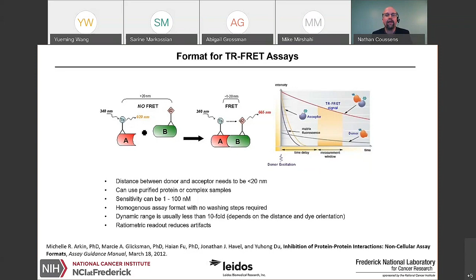And the advantage here is that when you initially excite the donor, you can also end up with unwanted sources of fluorescence coming from the matrix, from test compounds, but that drops off faster than when you make your TR-FRET measurement. So this ends up being a very clean measurement. The assay itself can be very sensitive with an excellent dynamic range. It's a homogeneous format. It's amenable to multiple time point reads. And in addition to being able to measure the TR-FRET signal, you can also measure the donor emission. And this allows you to identify some types of test compounds that can interfere with your assay.